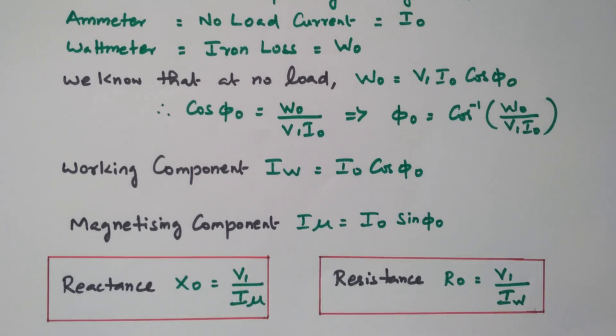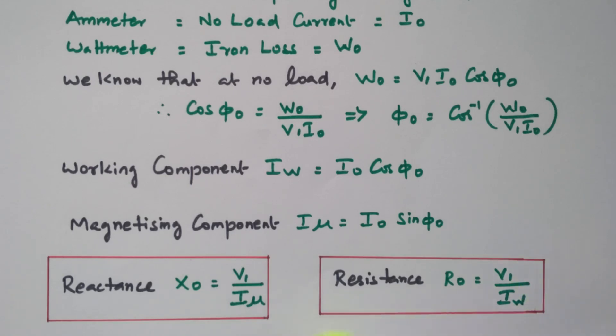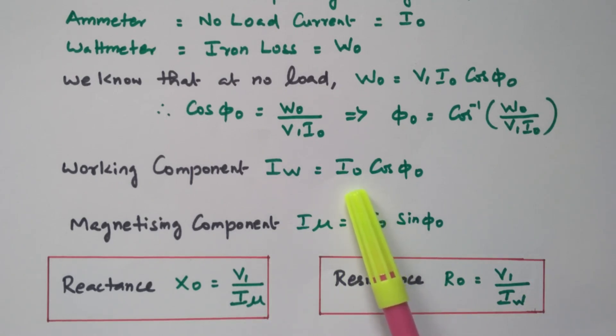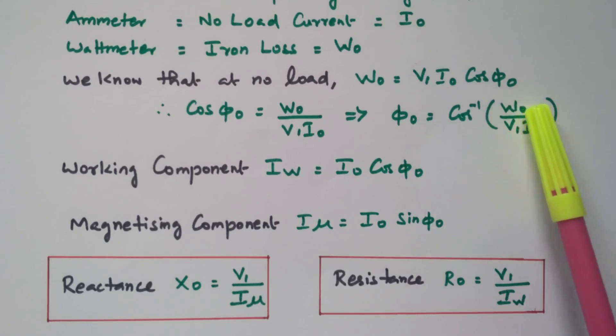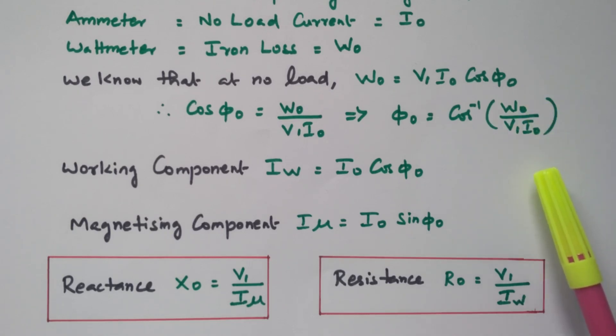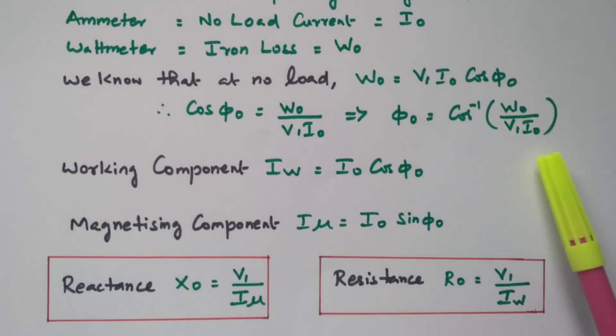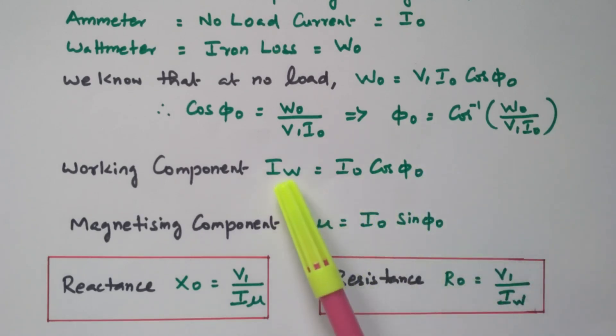In summary, the open circuit test gives us X₀ and R₀. The rated voltage V1 is read by the voltmeter. Iw and Iμ are calculated from the formulas using I₀ — the no load current from the ammeter — and φ₀, which is calculated from W₀ (wattmeter reading), V1, and I₀. W₀ is the power input to the primary winding, representing only the iron loss since copper loss is negligible. From the wattmeter, voltmeter, and ammeter readings we calculate φ₀, then Iw and Iμ, then X₀ and R₀.